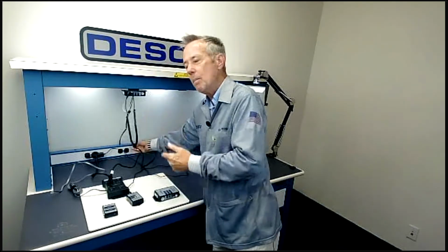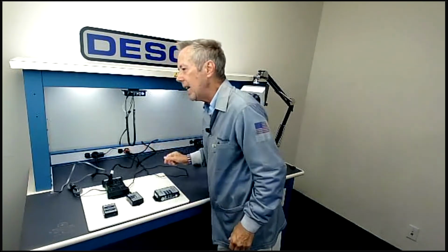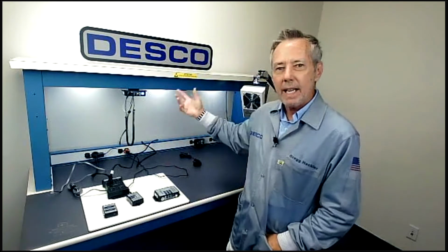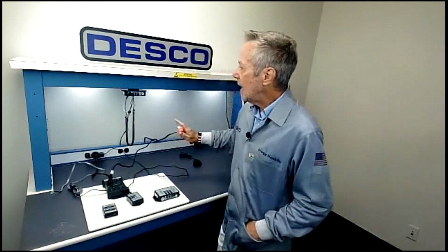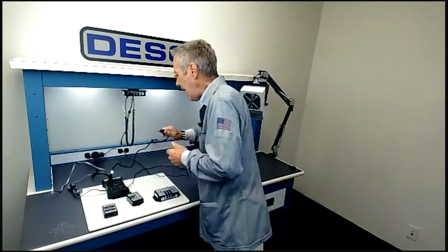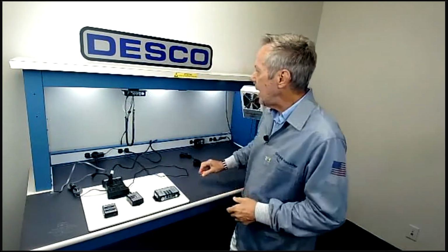So far, you've noticed the monitor has been very quiet. Okay, I'm going to plug this back in, and now you're going to get that obnoxious alarm and warning letting you know that I've lost my AC ground. That's the only single wire monitor that allows you to have that feature or that warning system. All right, so I'm going to plug that back in.